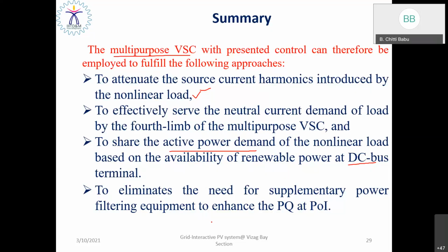So this is the work we have done so far, and we are still actively working on improving the capability of the grid-tied solar PV system during grid abnormalities, especially under grid fault condition. We haven't yet attempted to find a solution when the grid is under fault, because a fault is a highly transient and very abrupt change in the grid voltage. We are actively working to find a very robust control technique to improve the power quality, as well as the power management, when the grid is under fault condition.